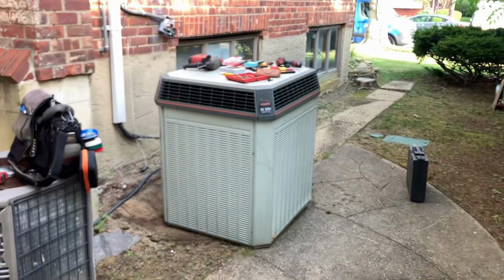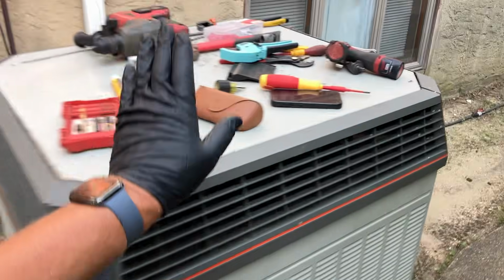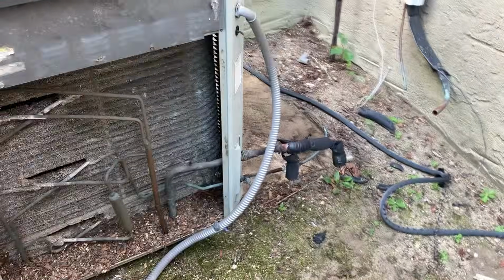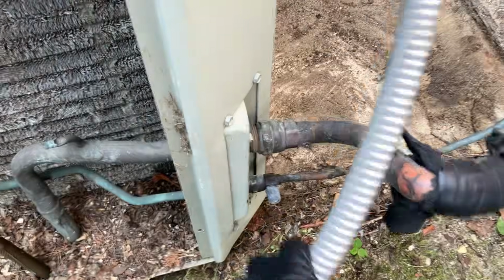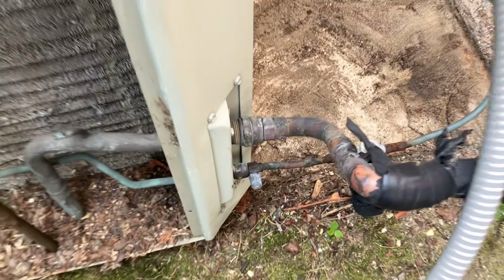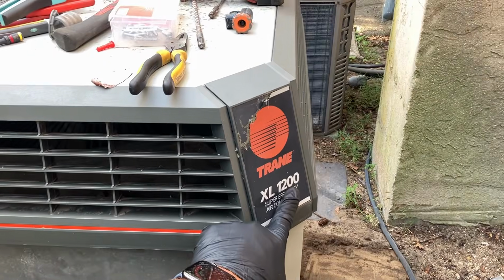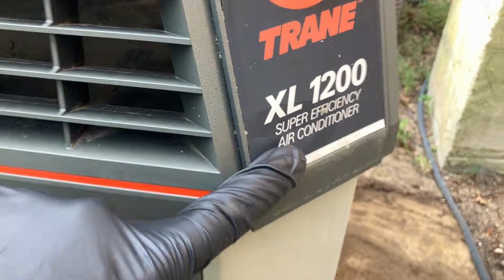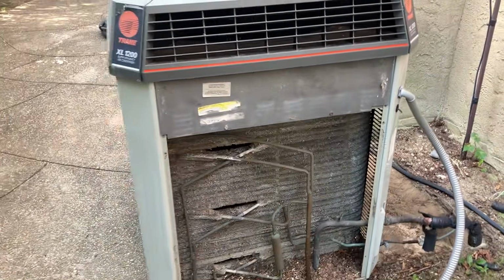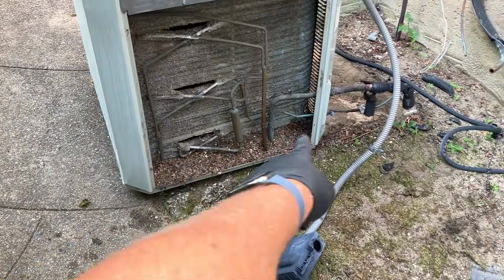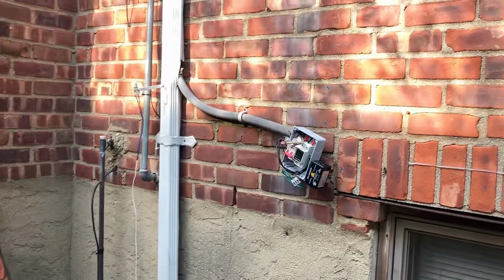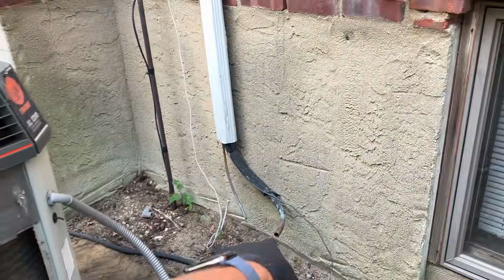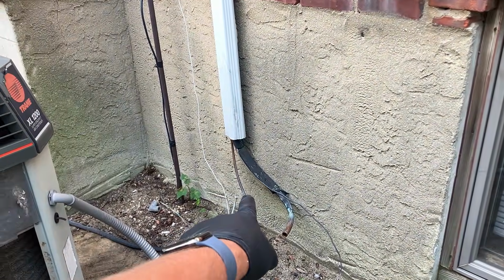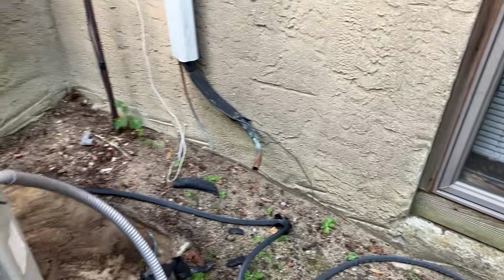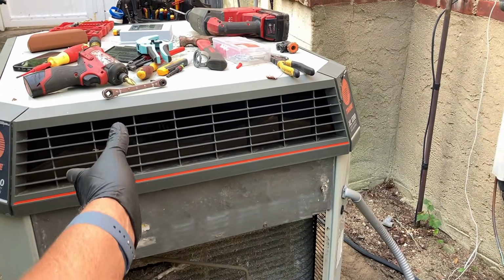All right, 10 minutes after 8 here. The refrigerant has been recovered. I haven't seen this in forever, there's no service valves on the condenser. This Trane XL1200 super efficiency air conditioner is definitely an old wildebeest that's likely never been serviced properly. This is disconnected. I have a 7/8 and 3/8 line set coming from the evaporator coil in the attic, and also our communication wire, which carried 24 volts to close the contactor.